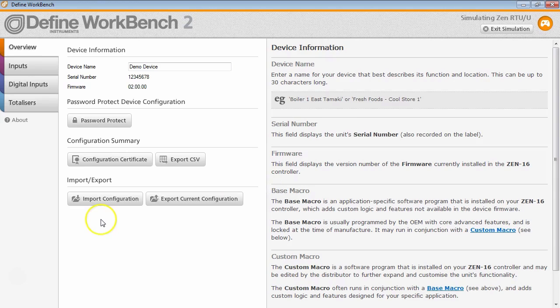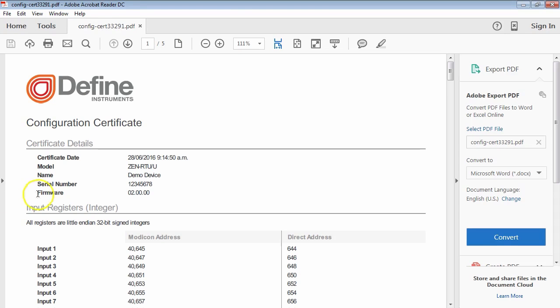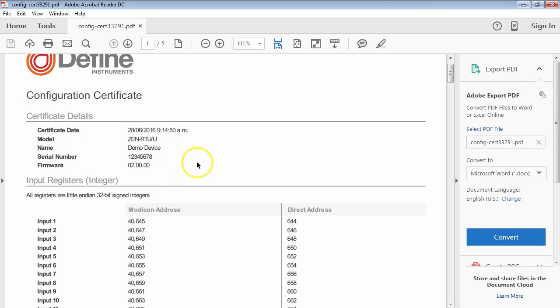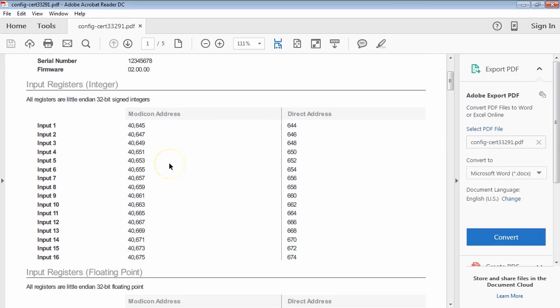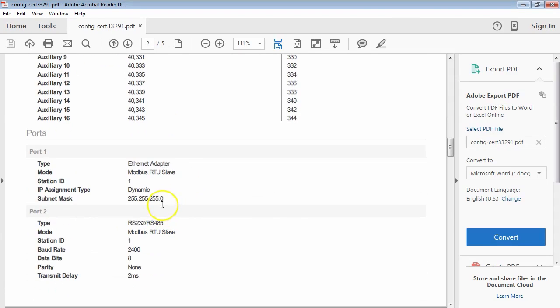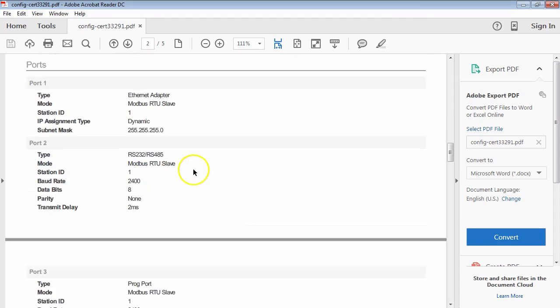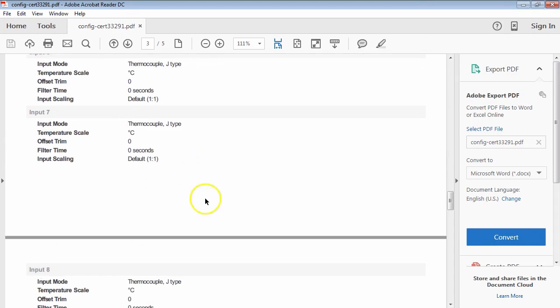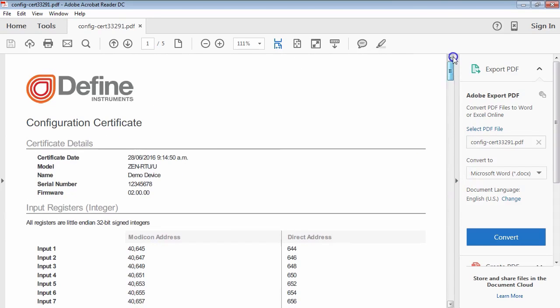If you're using the Zen RTU primarily with SCADA or PLC, then you'll be talking to it in Modbus, either Modbus RTU or Modbus TCP. And probably the most important thing you want to know is the registers. So we've got two options for you to get that information. One is to export a configuration certificate. This is a PDF type certificate as shown here, and you'll notice that it gives an overview of the device, and it has registers and then a setup showing you setup of ports, input modes, etc. So that's a printable form.